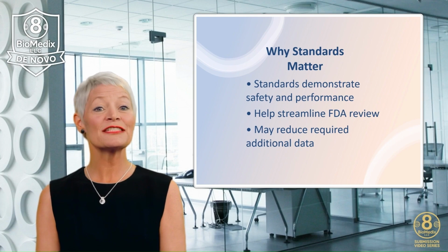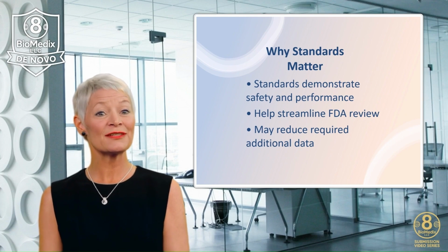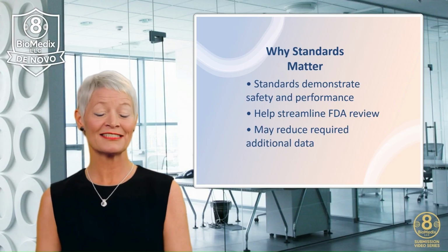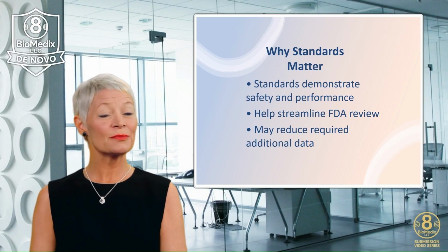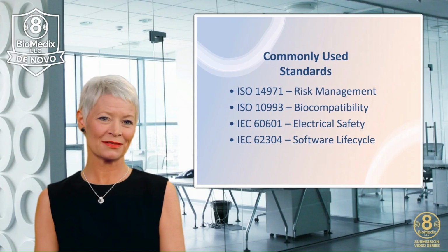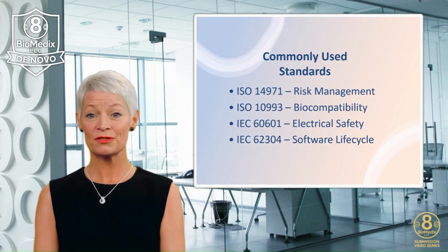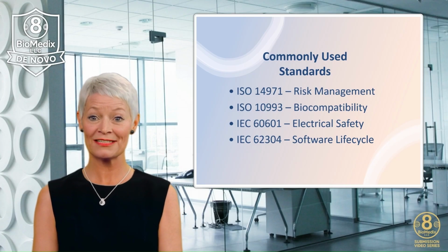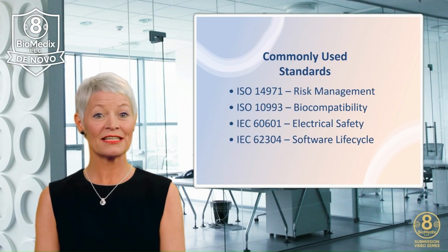Commonly used FDA-recognized standards include ISO 14971 for risk management, ISO 10993 for biocompatibility, IEC 60601 for electrical safety, IEC 62304 for software development and lifecycle documentation. The FDA maintains a searchable recognized consensus standards database, accessible on the FDA's website.